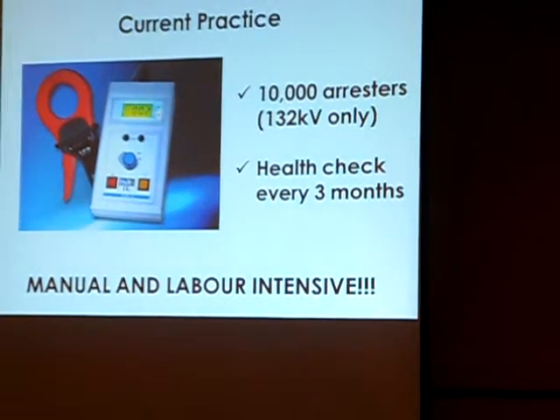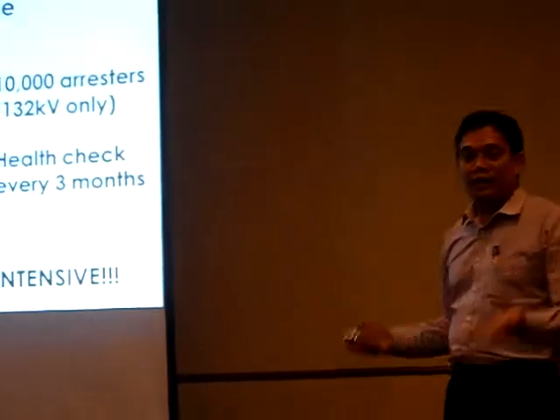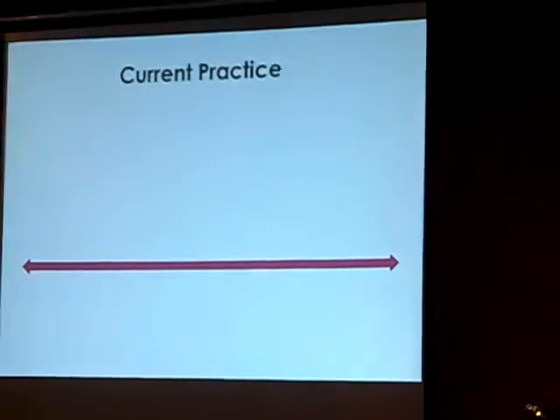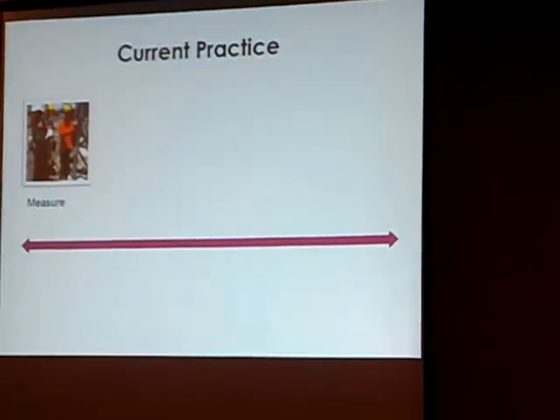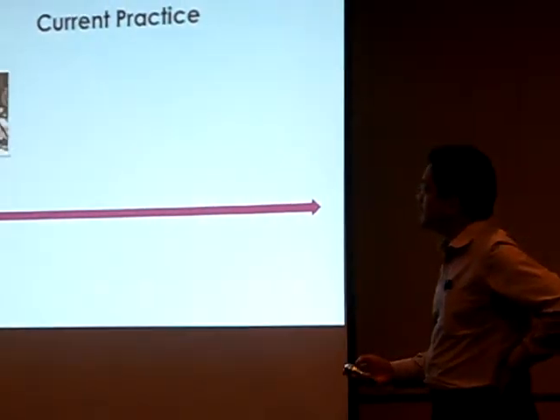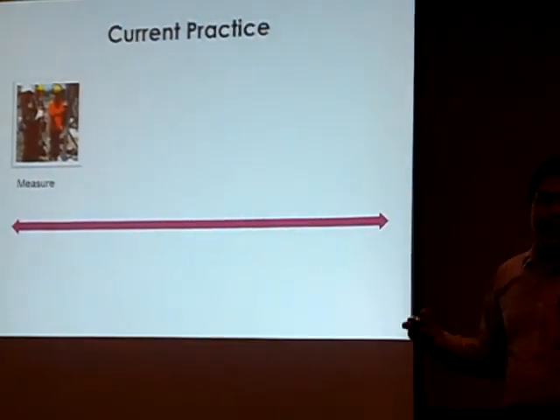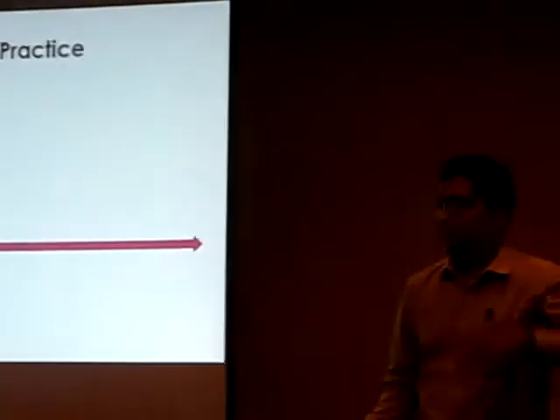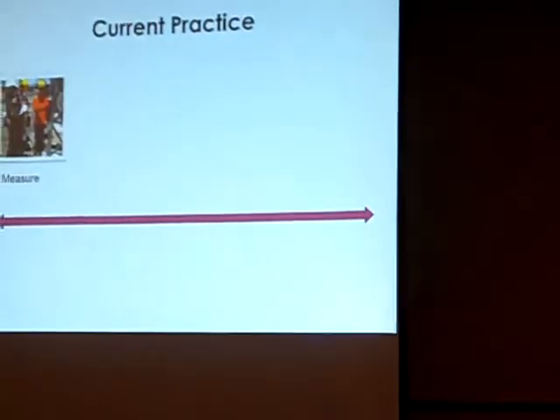So what's the issue here? It's manual labor, and manual labor is labor intensive. Let me show you what I mean. In current practice, when the time comes, they go to the substation, connect the clamp to the bottom of the arrestor, which is safe by the way, and measure the leakage current.